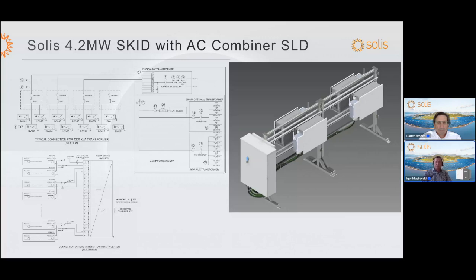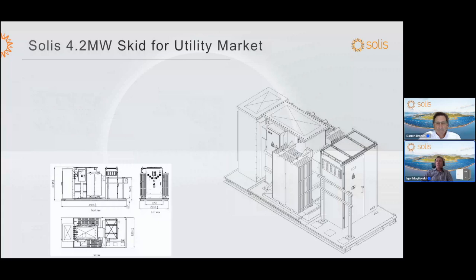It comes with a standard 5 kVA auxiliary transformer with a 120 amp circuit breaker and an optional 30 kVA transformer for trackers that is 480 volt rated. It also comes with a communication control that could be installed in the skid as well. Here's the mechanical design of the skid. Like I mentioned, 4.2 megawatt. The transformer is rated 34.5 kV and 800 volts. On the low voltage side, it comes with different vector groups: DY1, DY11, and YG.